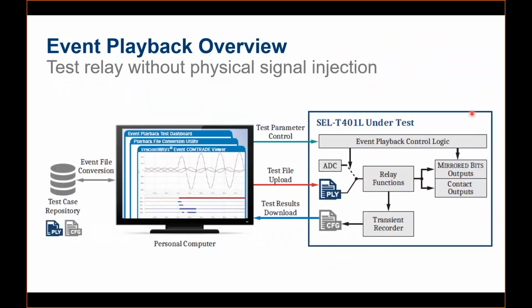Okay, lastly, because this session is mostly related to testing, we have a tool inside the software and inside the relay to simulate your real-time faults in the relay without using any test set. You can use any kind of event records from your relays. It may be SEL relays, non-SEL relays, or some high-sampled COMTRADE files if you have. There is a utility inside our software that will convert it to a file that is compatible with the relay. So you don't need a test set to evaluate or study any event record. If you have the COMTRADE from the field, you can just use that utility. We call this the event playback utility.